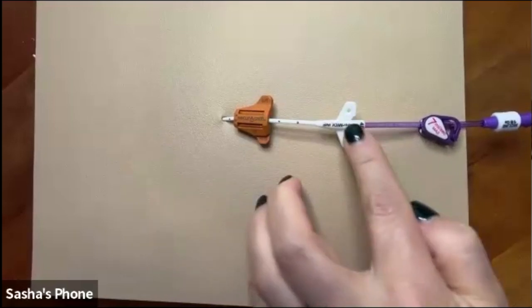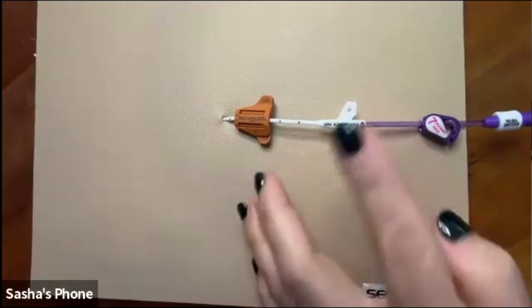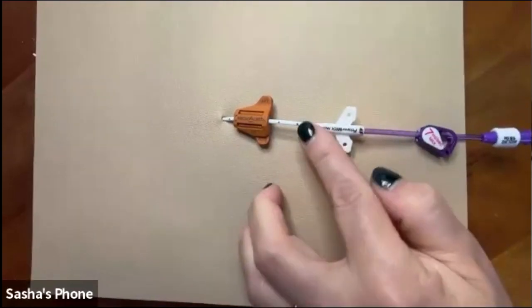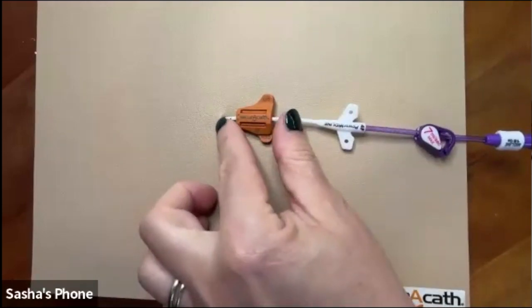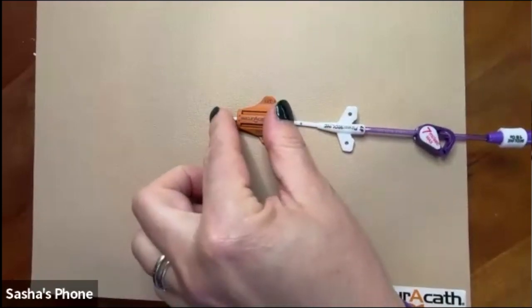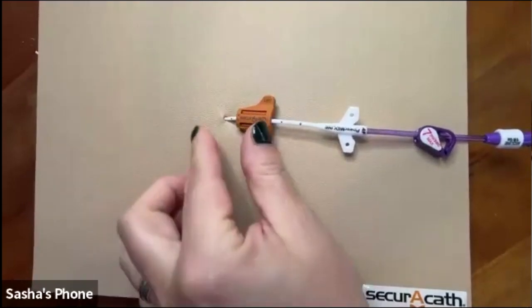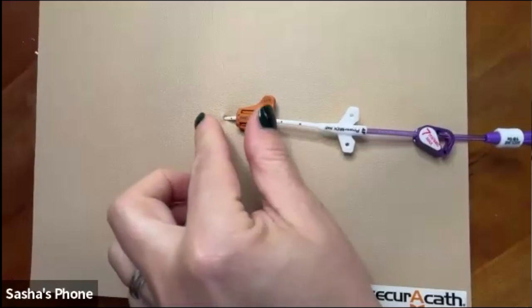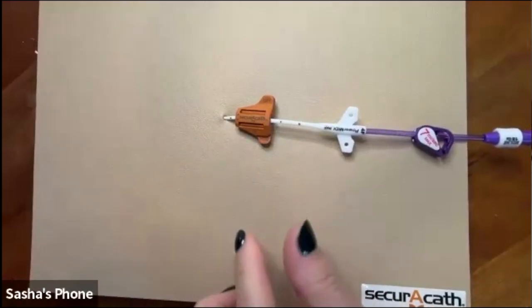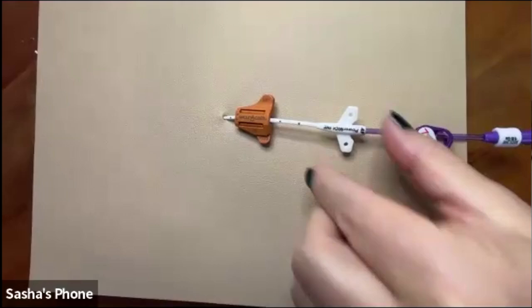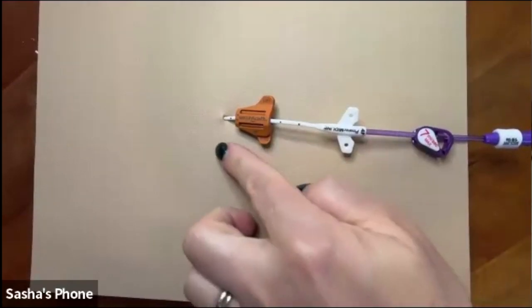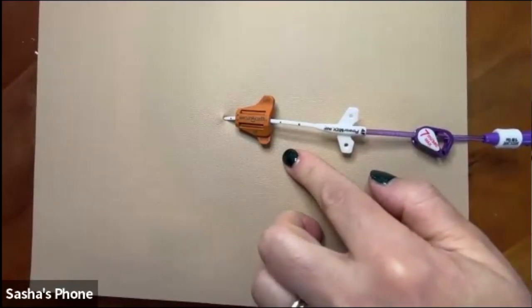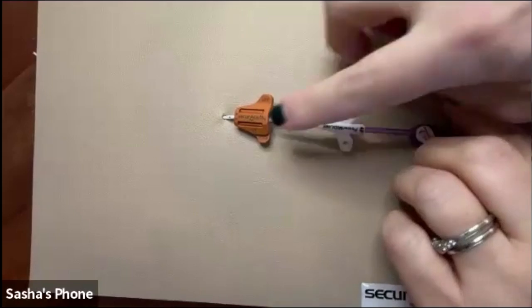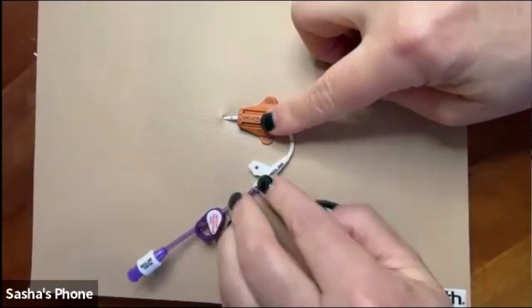But as far as positioning for the device, you can see that this is, I guess, a typical PICC catheter. This could be a tunnel line as well. The device itself is 3 centimeters long. So when you put in a SecurAcath, you have to make sure that you have at least 3 centimeters of catheter available. But really, you want a little bit more than that. So typically, I would plan for 5 centimeters external because it allows you to make a nice little loop.